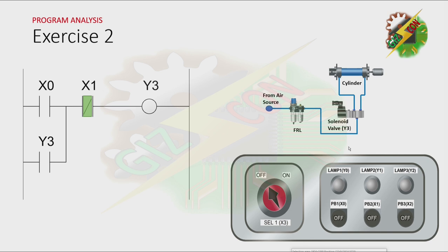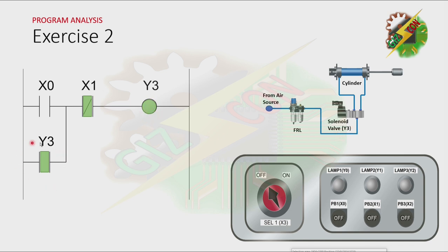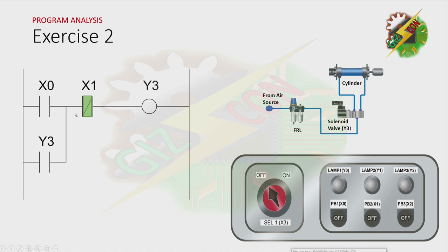Let's press PB1. As you can see here, when you press PB1, X0 is activated, and that will cause Y3 to turn on, which is the solenoid. And because there is latching here, Y3 will not turn off. The only way to turn it off is by pressing PB2, which is X1.